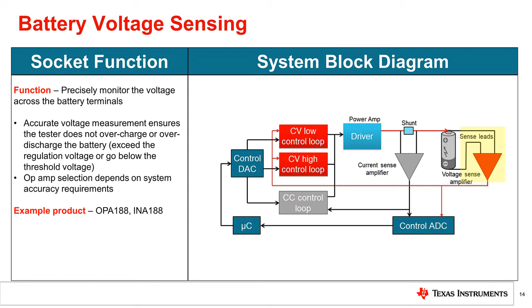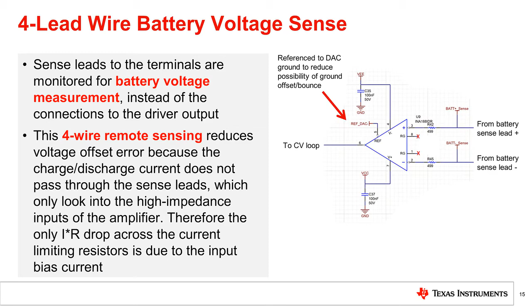It should be noted that for most BTS implementations, 4-lead sensing is used instead of local or 2-lead sensing. This means that instead of measuring the battery voltage using the same leads that are utilized to charge or discharge it, independent sense leads are monitored instead. Without this, an offset that is a function of the charge-discharge current and connection parasitics will appear. With independent sense leads, the only apparent offset is that across the current limiting resistors due to the input bias current, and this can be addressed via calibration.